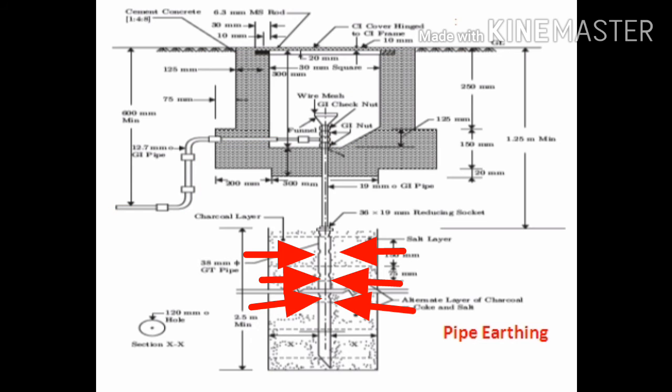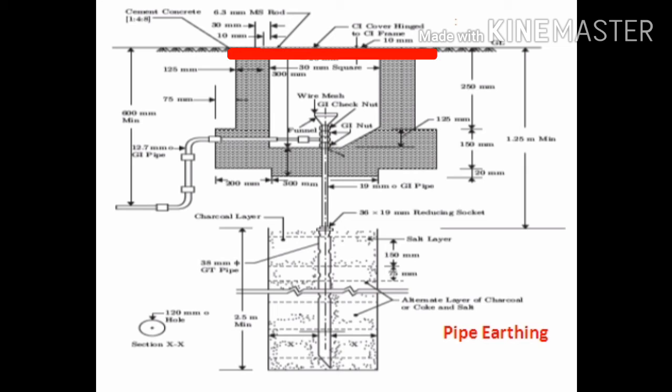The holes are drilled on the GI pipe of 38 millimeter that is buried inside the layers of charcoal and salt. Through these holes, the water poured into the funnel reaches the charcoal and salt layers. All the connections that are made in this type of earthing are by means of GI nuts and bolts in order to avoid rusting. The entire earthing system is covered by cast iron cover. The earthing wire runs up to the metallic casing of electrical load through a GI pipe.